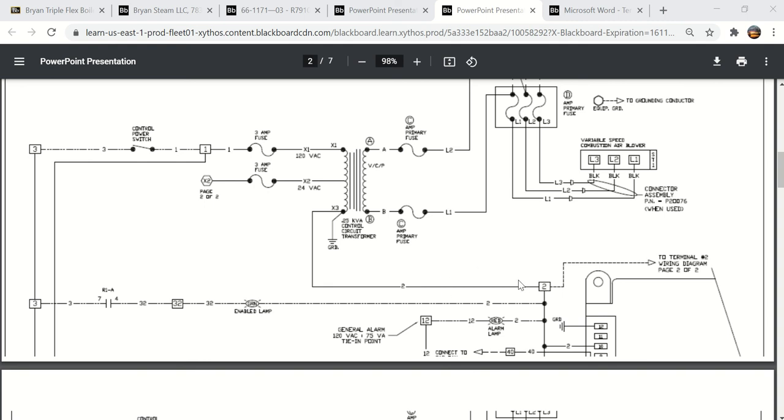We would actually put the coil of a relay power on one side of the coil, common to the other side of the coil, and just like this red lamp, anytime that coil energized, it would close a set of contacts, and that's how we would indicate to our building automation system maybe that there is an alarm. Maybe you want to put a light outside the boiler room door that shows when the boiler is in alarm.